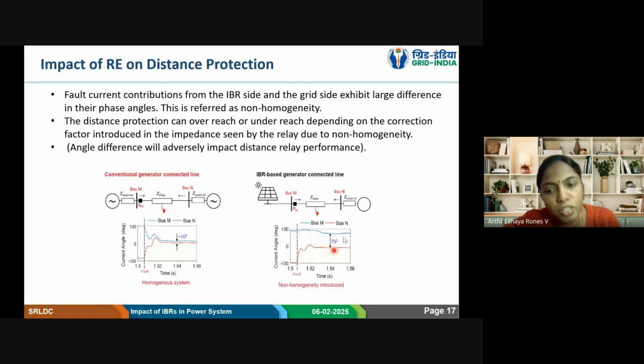Why are we bothered about this angle? In the distance relay calculation of the phase loop and earth loop, this angle is involved, and because of this, there is a correction factor involved. We are simplifying the phase loop and the earth loop, assuming this angle variation is very minimal. If that assumption is not valid, we will have one more component, and that component can be a plus or a minus, depending on the variation of this angle. When it is plus, the relay will overreach. When it is minus, the relay will underreach. So that is how the RE is impacting the distance protection.